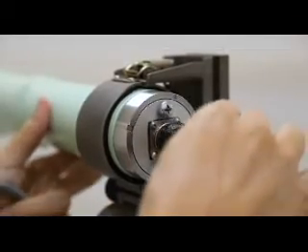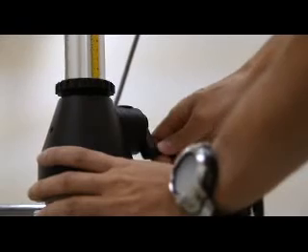The meter to be calibrated is received by the qualified personnel working in the laboratory. Receipt of the meter for calibration is recorded in the database. This recording procedure serves to identify any instrument received, to check its progress through the process, and provides easy overviews of calibration history. After the recording procedure, the meter is mounted on the calibration bench using various jigs and fixtures. Depending on the type of meter being calibrated, we provide either versatile or tailor-made holders. After mounting, the meter is targeted using lasers and accurately positioned.